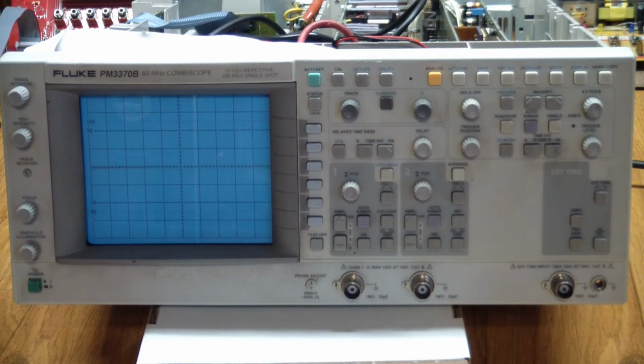Well, I let it run for a while, and I was in the room cleaning up a little bit and looking for stuff and hoping I'd find my HV probe, when I heard a really loud crack coming from the instrument. I ran back. The instrument had turned itself off. There was no magic smoke. There were no bad smells, nothing. It just turned itself off.